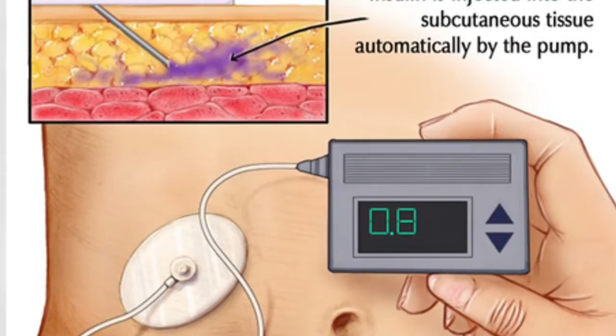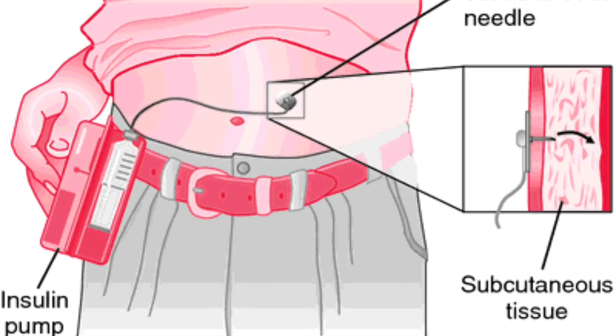The pump has an insulin reservoir within which it contains short-acting insulin, which begins to have an effect within 30 minutes of delivery. The user must program the pump to release a bolus, which is an extra amount of insulin released to cover the expected rise in blood glucose following a meal, which is based on the amount of carbohydrates in the meal. Basal insulin is delivered continuously over 24 hours to regulate blood glucose between meals. This rate can be programmed depending on the time of day, for example, more during the day and less during the night, and then the pump is often clipped onto a belt or worn otherwise near the skin.